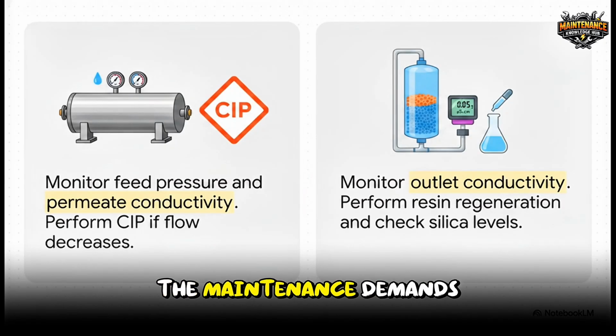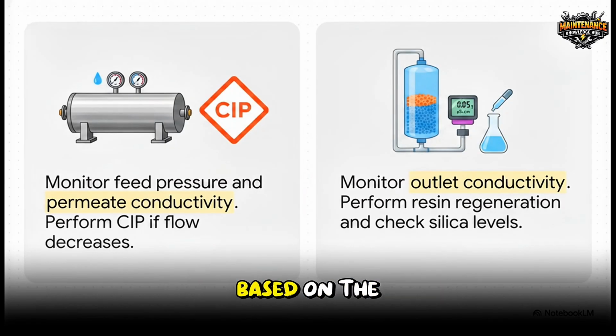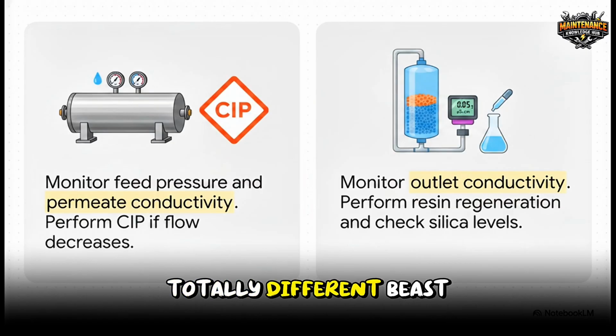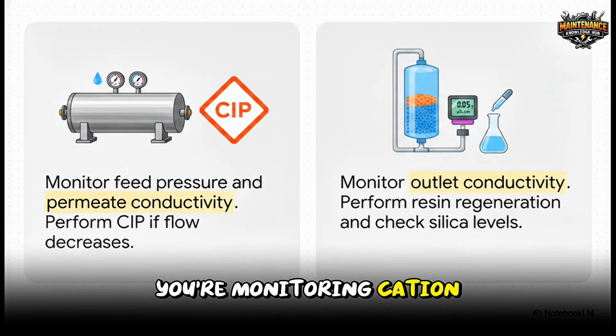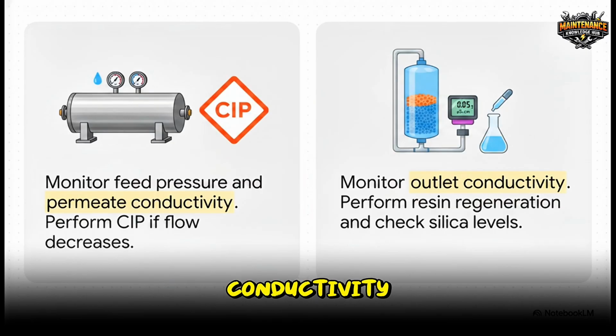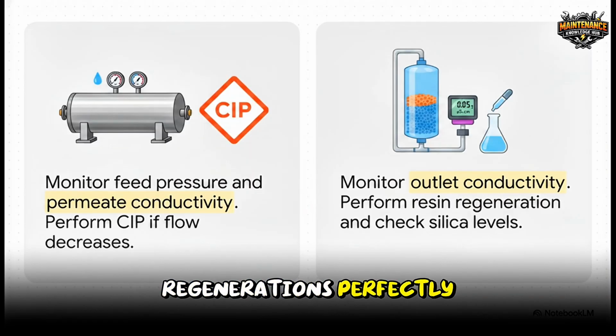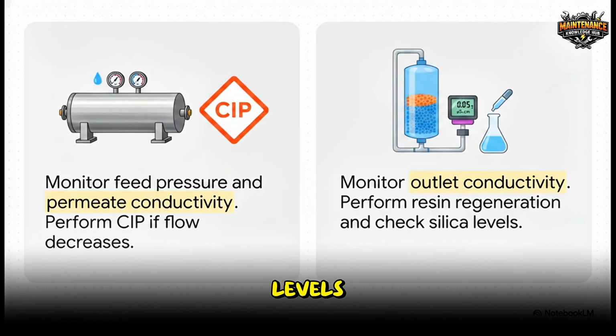Now notice how the maintenance demands absolutely diverge here based on the specific system. With your RO, or reverse osmosis plant, you are hyper-focused on pressure differentials. You have to trigger a clean-in-place procedure if permeate flow drops even 10 to 15%. Meanwhile, your demineralization, or DM plant, is a totally different beast. There, you're monitoring cation and anion outlet conductivity, timing your resin regenerations perfectly, and tracking those mixed-bed silica levels.